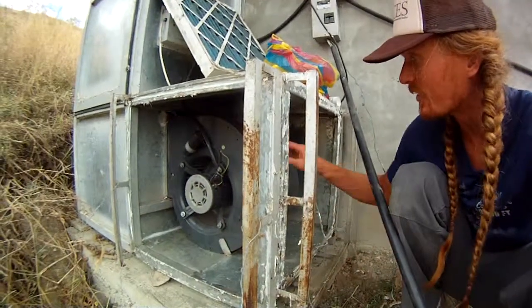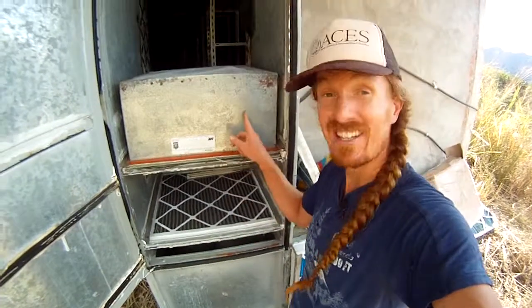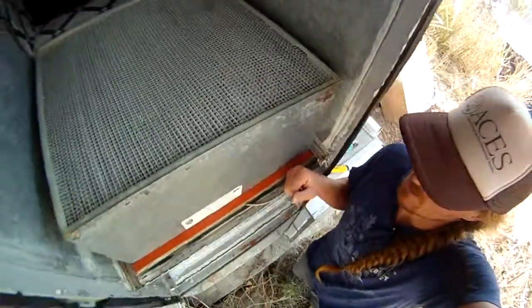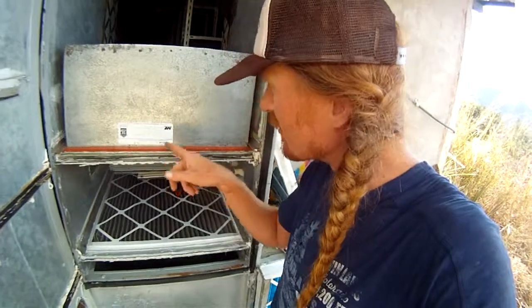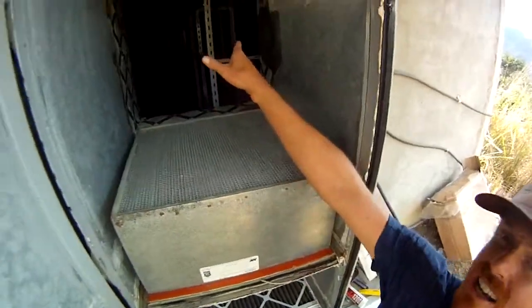So this is the inside here — gives you a good idea. It's a nice big blower. So what's behind the door? This is the push side of the filtration system. This is another pre-filter, and this is the HEPA filter. Thick, beefy, true HEPA filter — this thing is a foot thick of glorious happiness. As you can see right here, it is 99.99% efficiency. This is the main thing. It's blowing out this way and into the lab, where that lab is nice and clean.